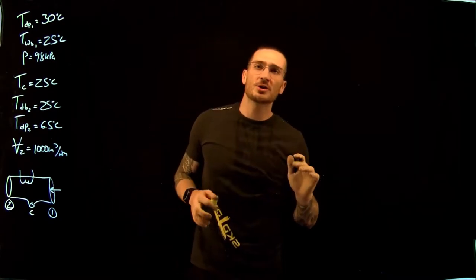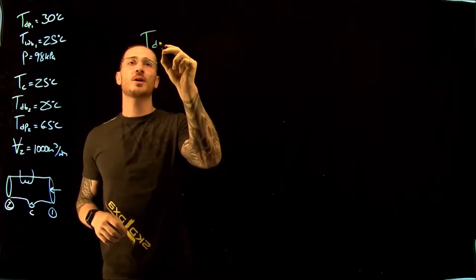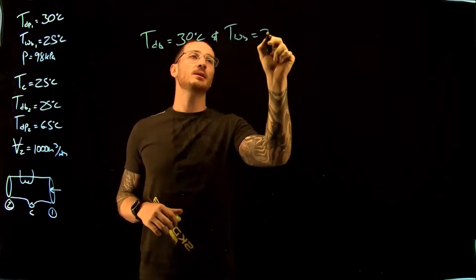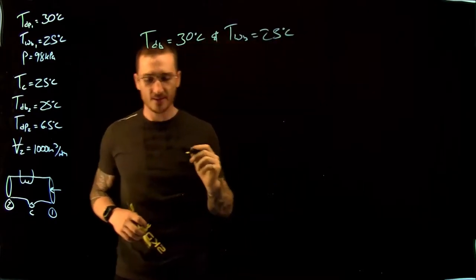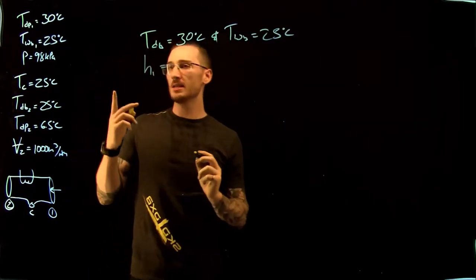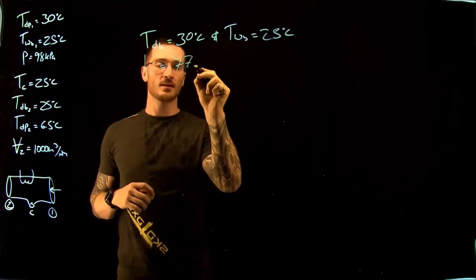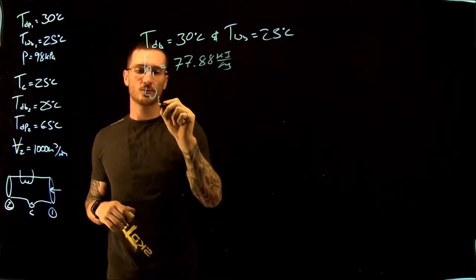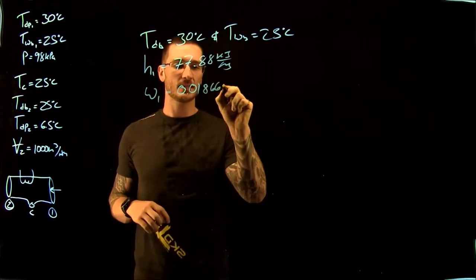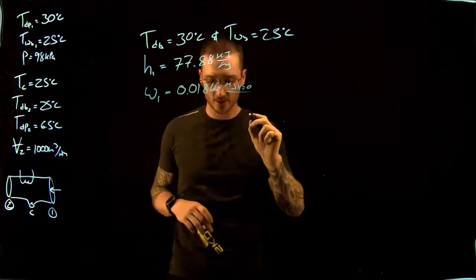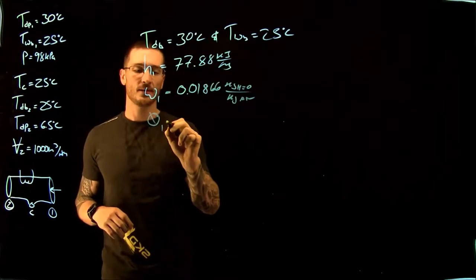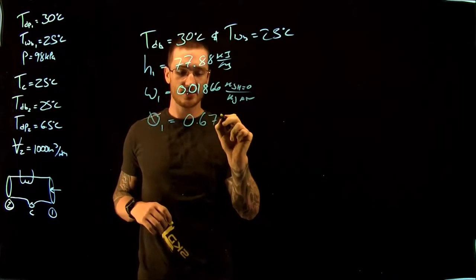From our psychrometric charts, at a dry bulb temperature of 30°C and a wet bulb temperature of 25°C, we can find that enthalpy at point 1 is equal to 77.88 kJ/kg, the specific humidity at point 1 is equal to 0.01866 kg of water per kg of air, and the relative humidity at point 1 is equal to 0.6721.